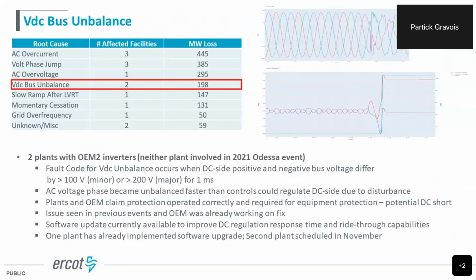So what happens is you have a voltage disturbance on the grid side, and then you have unbalance on the phases, and then the DC side regulation cannot recover quickly enough, cannot regulate quickly enough. So you have unbalance on the DC side by either over 100 volts or 200 volts, major versus minor. And that tripped off all the inverters at two different facilities here.